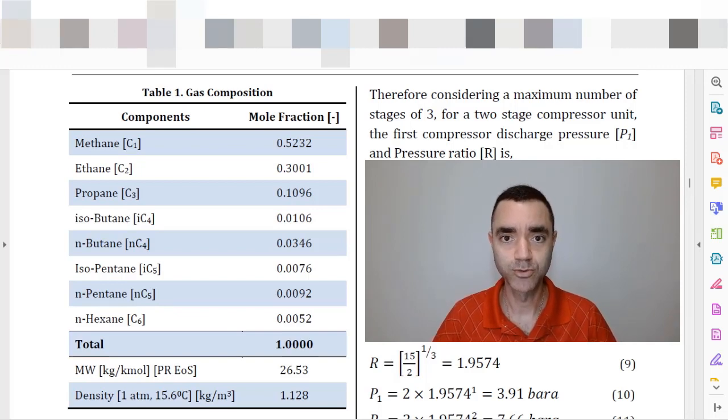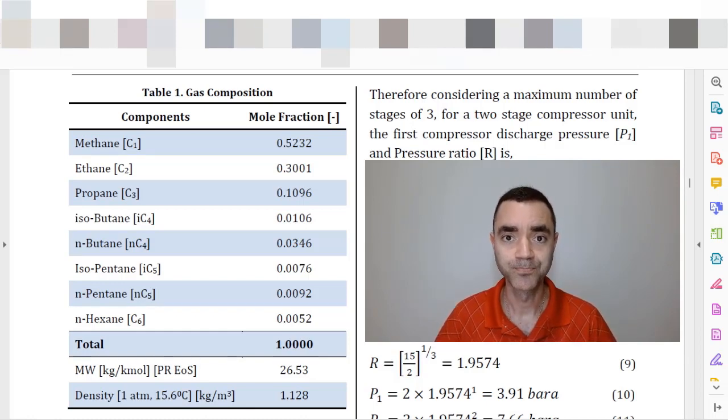To perform the evaluation, you need to know the gas composition of the stream — available in Table 1 — and also how to define the discharge pressure of each stage of compression. To understand why we have multi-stage compression: when gas is compressed, the temperature of the fluid increases, and that can lead to hazardous conditions. For flammable gases, there is an auto-ignition temperature to avoid. Other fluids can experience polymerization or have a degradation temperature. For compressors with lubricants, high temperature can lead to combustion of the lubricant. So we limit the maximum temperature by defining the maximum compression ratio of each stage.